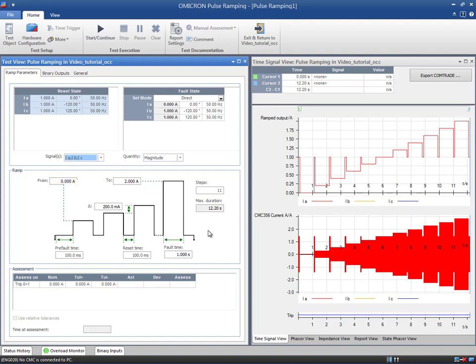The pulses will be increased by Delta until the end value is reached. To determine these settings, we will follow the same theory that we recommended in the Ramping module. The Ramp will range from 80% to 120% of the high set value. As Delta, we will take the current tolerance from the manual divided by 4.